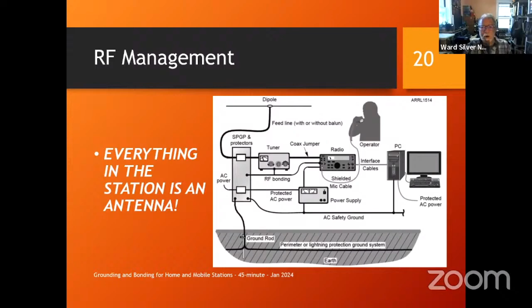Again, forget about an all-band RF ground. That doesn't exist. There's no 0 volt anything. What you want is to concentrate on bonding, so you have 0 volt difference. You don't want the differences. Whatever that voltage is, you want it to be the same everywhere in the station. You do that with bonding with electrically short conductors. That keeps it all at the same voltage so you don't have current flowing because of RF voltage differences.